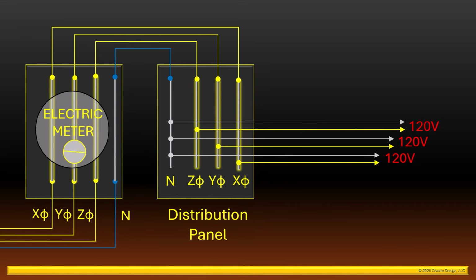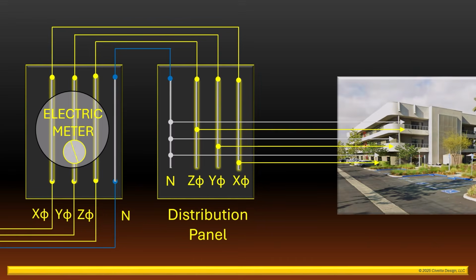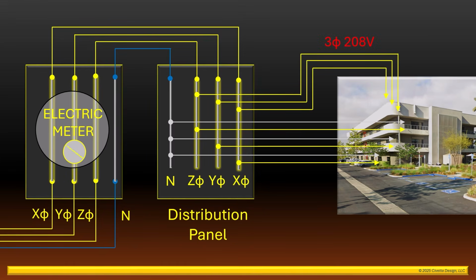Because of the ability to utilize all three windings to produce single-phase 120-volt power, this type of transformer is very popular with office buildings. For example, in this three-story office building, the entire first floor can be energized using the X phase, the second floor with the Y phase, and the third floor with the Z phase. The three-phase 208-volt power can be routed to the roof to provide power to the air conditioning and the elevator motors.